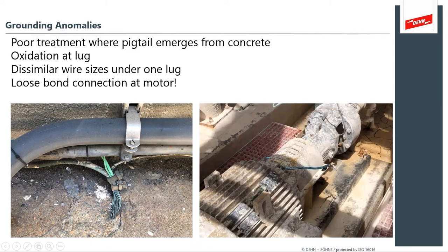So it's going to be very difficult to troubleshoot problems with the instrumentation when it's floating bonded. So here we have a direct problem where the instrumentation and the earthing on this motor is going to lead to instrumentation failure because the motor is not bonded.